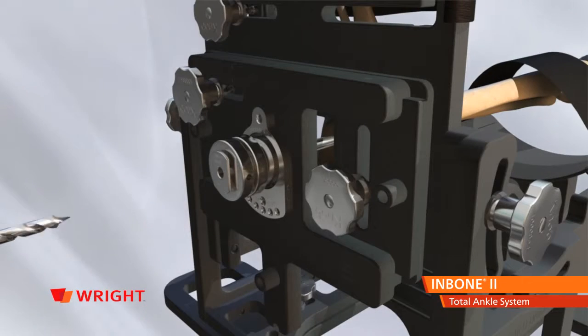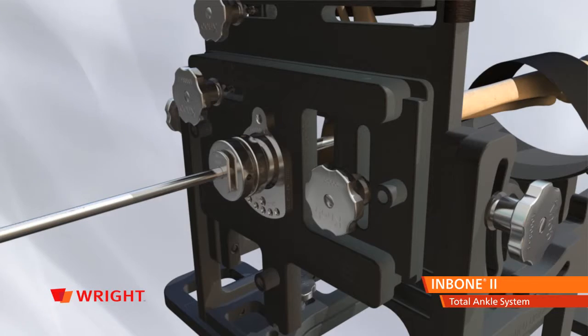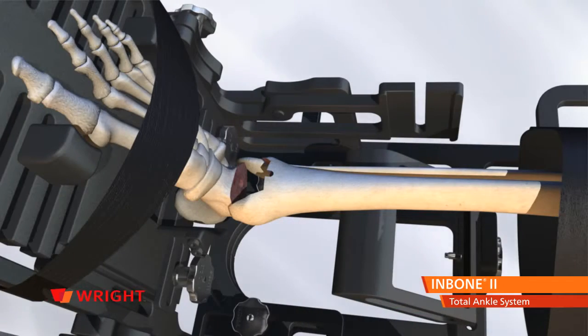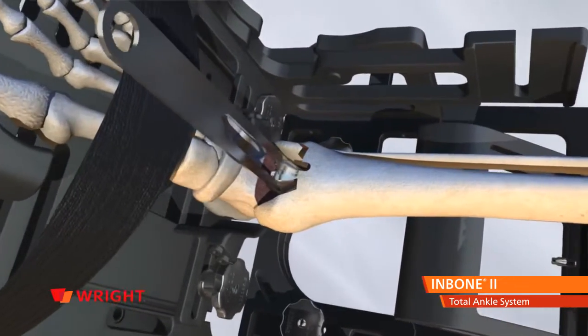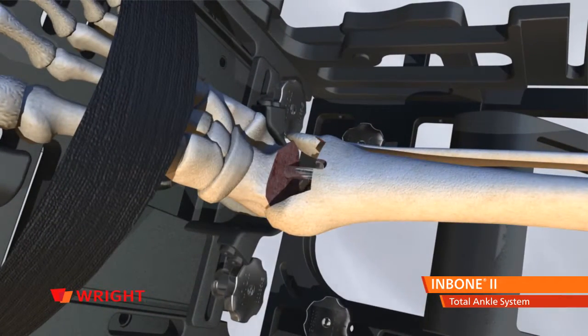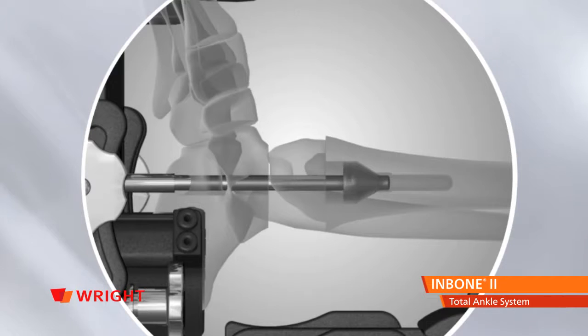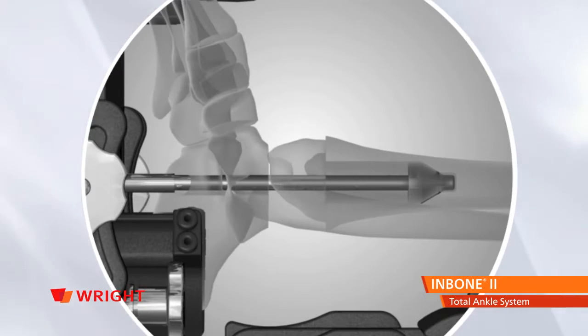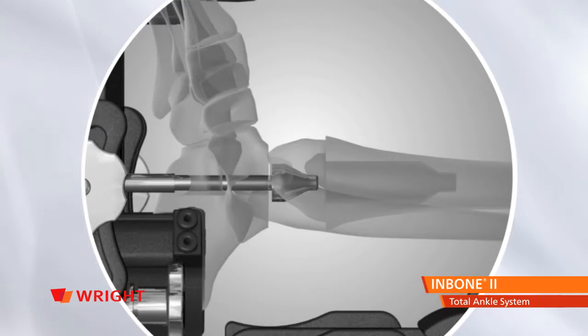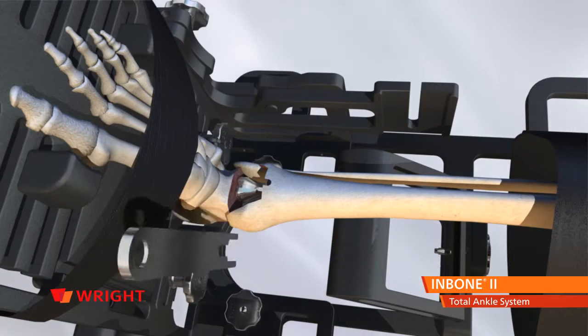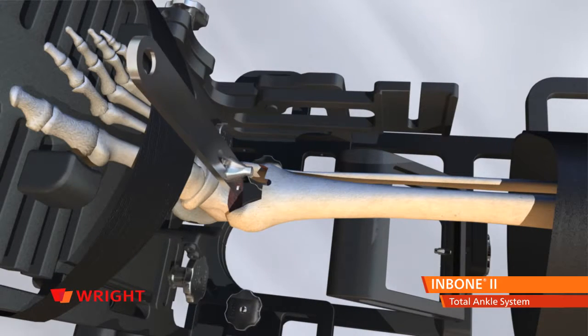Remove the 6 millimeter drill and replace it with the drive rod. In the visible joint space, connect the reamer tip to the drive rod using the appropriate size clip and reamer tip. Ream to the desired depth based on the number of stem pieces previously templated. While turning clockwise, retract the reamer into the visible joint space. Install the tibial stem wrench on the flats of the reamer tip and unscrew it from the driver.